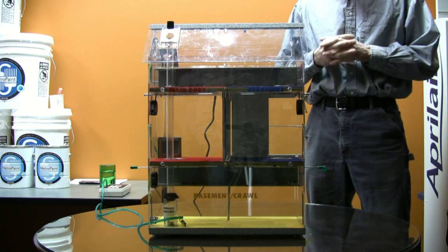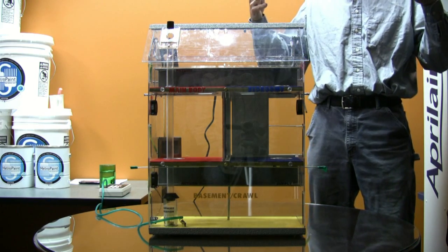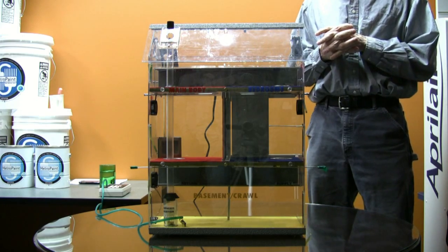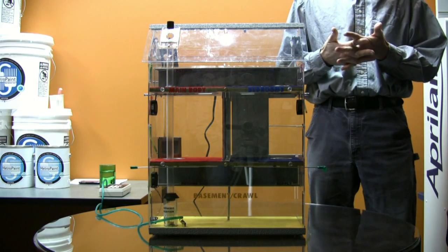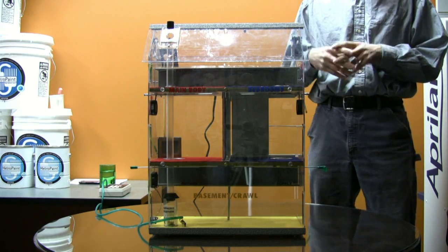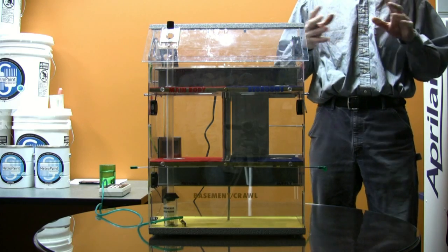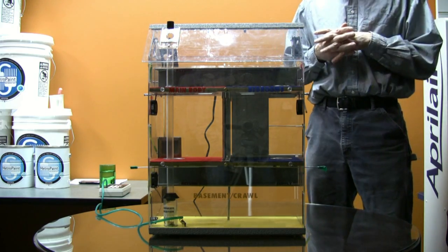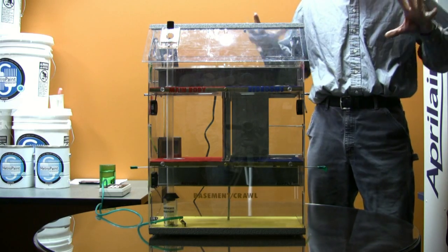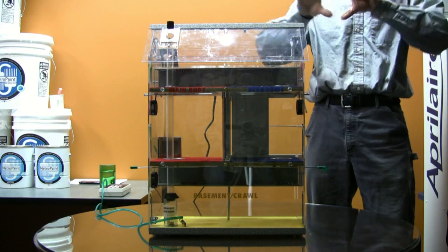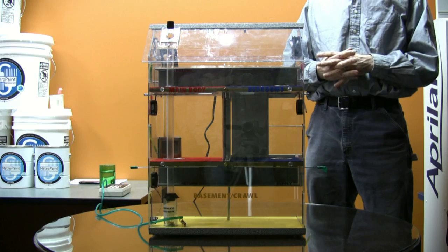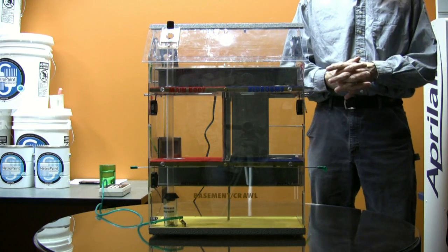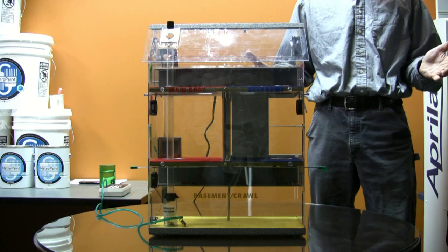I've seen homes where the sheathing of the bedroom walls was entirely rotted because they didn't have any pressure relief for the bedroom. Basically, they had multiple layers of carpet, a tight-fitting door, and no return air for that room. So every time the heat was running, that room was positively pressured, and it forced all that moisture into their walls through leaky electrical outlets and under and around the drywall, and it rotted out their building.